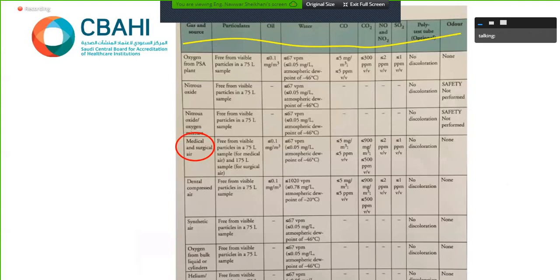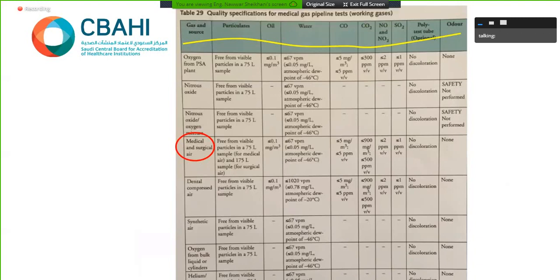In HTM, for medical air, it gives us the parameters in terms of oil, water, CO, CO2, odor, etc. So this is the value that we have to see. If it exceeds it, it means the medical air purity is not acceptable.